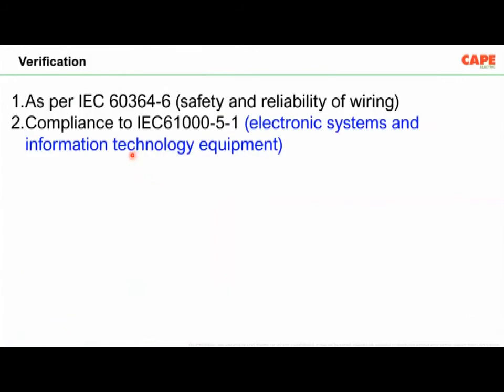Now, the last part. Whenever your electrical system is completed, we are supposed to verify the system, which includes inspection and testing. Similarly, for an electronic system, during or after commissioning, we are supposed to comply as per the IEC 61000-5-1 standard for electronic systems and information technology equipment. After installation, we are supposed to do testing, and I'm not talking about the testing of an electrical item or a device. I'm talking about testing of the entire system, starting from probably a UPS and all the items connected on the electrical network. So this testing is also compulsory. Most of you know the IEC 60364 10 tests are recommended in our IS 732, but mostly we don't do it.